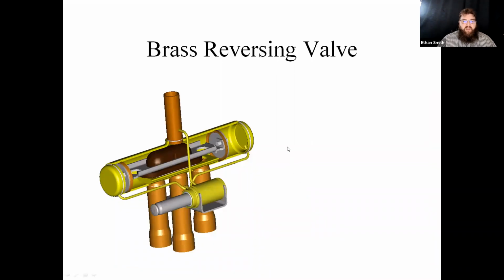We get the reversing valves that we talked about quite a bit. This is kind of a CAD drawing of a reversing valve. You see all 4 capillary tubes: one on the suction side, one on the high side, and then our 2 pilot tubes that go into either side of the diaphragm.